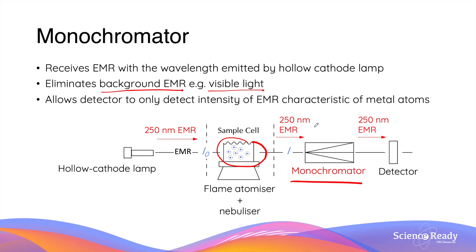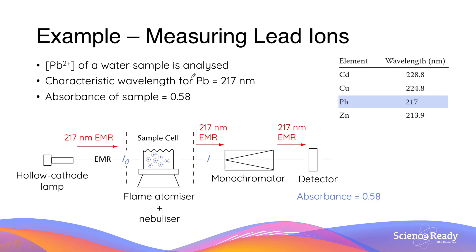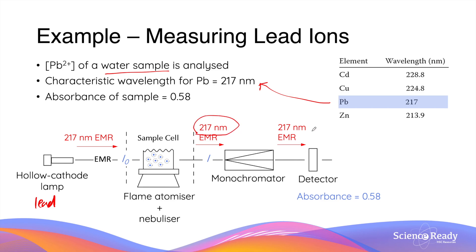Finally, the absorbance is calculated using Beer-Lambert law, comparing the final intensity with the initial intensity I₀. Let's summarise everything in an example: we want to analyse the lead concentration in a water sample. From the table, lead atoms absorb a characteristic wavelength of 217 nm. So we use a hollow cathode lamp made of lead to produce this EMR. As the EMR passes through the flame which atomises the water sample, part of the radiation is absorbed by the lead atoms present. When the EMR exits the flame, it is passed through a monochromator which only passes radiation of 217 nm, and then the detector measures the intensity of this radiation to calculate the absorbance.